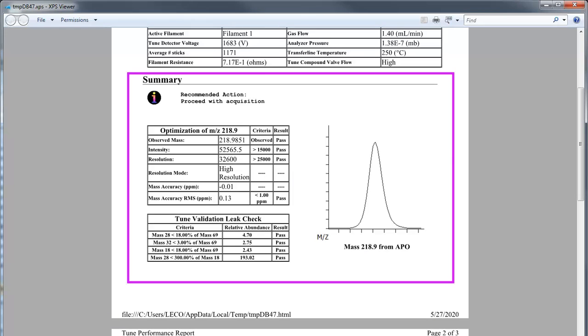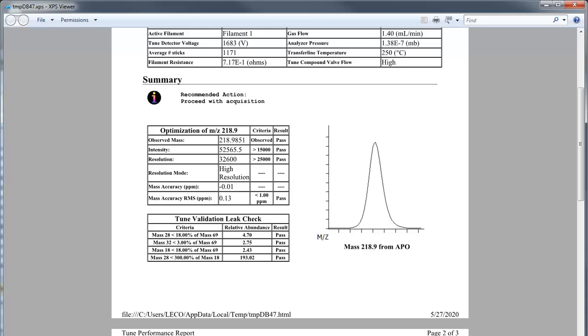The summary section contains recommended actions based on the current system status. The criteria include the intensity and resolution of mass to charge 219, the RMS mass accuracy in ppm, and the ratios of air and water to meet minimum leak check requirements. The summary section also provides data used for the report along with other data which can be used for comparison or to troubleshoot problems with the instrument.